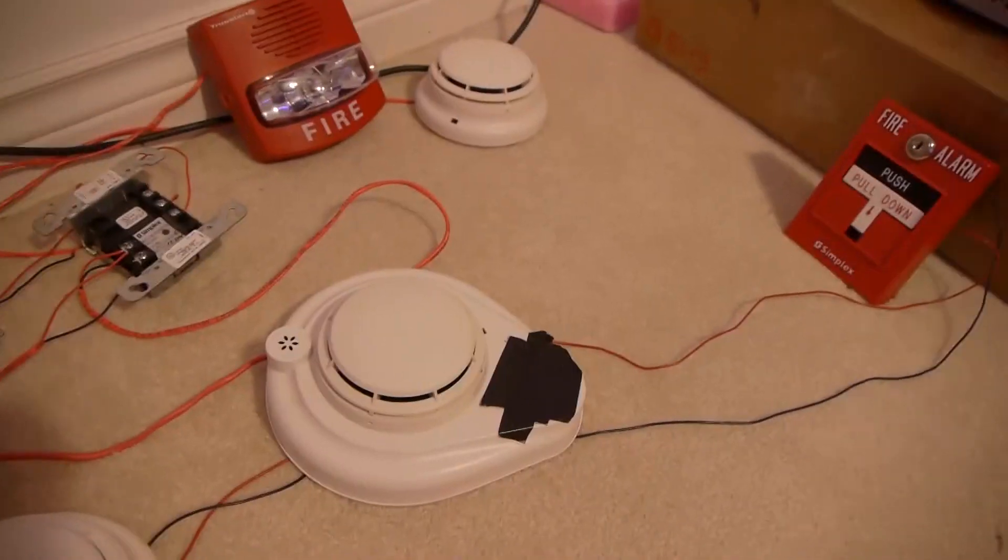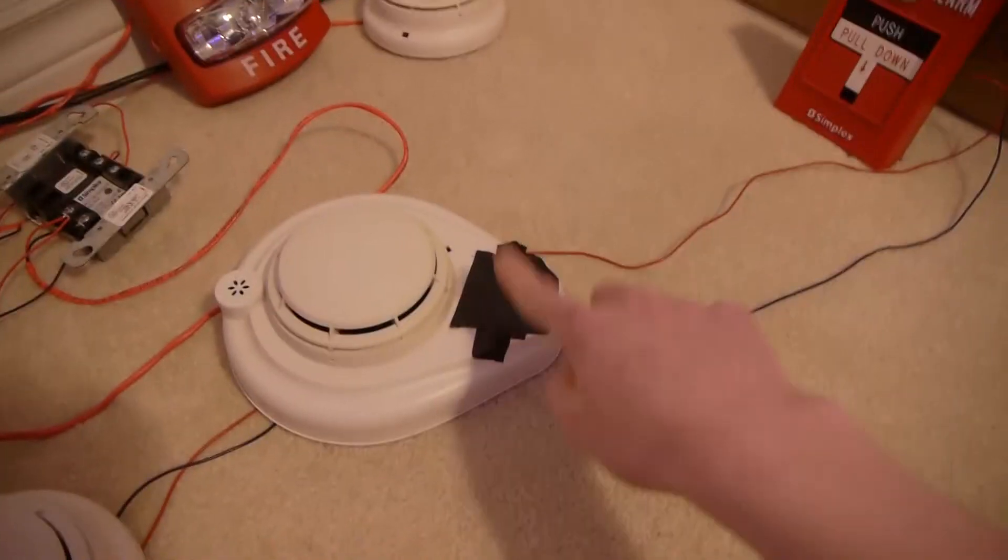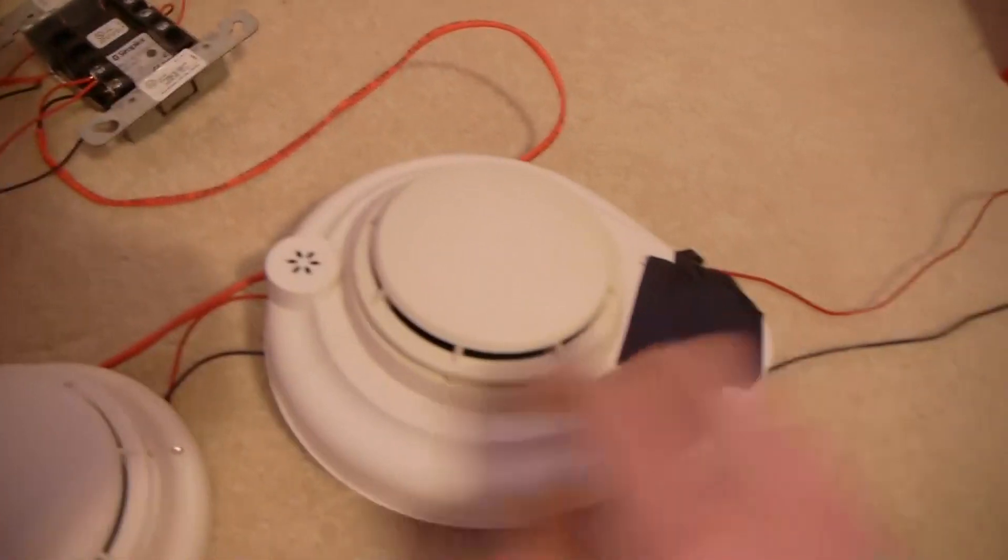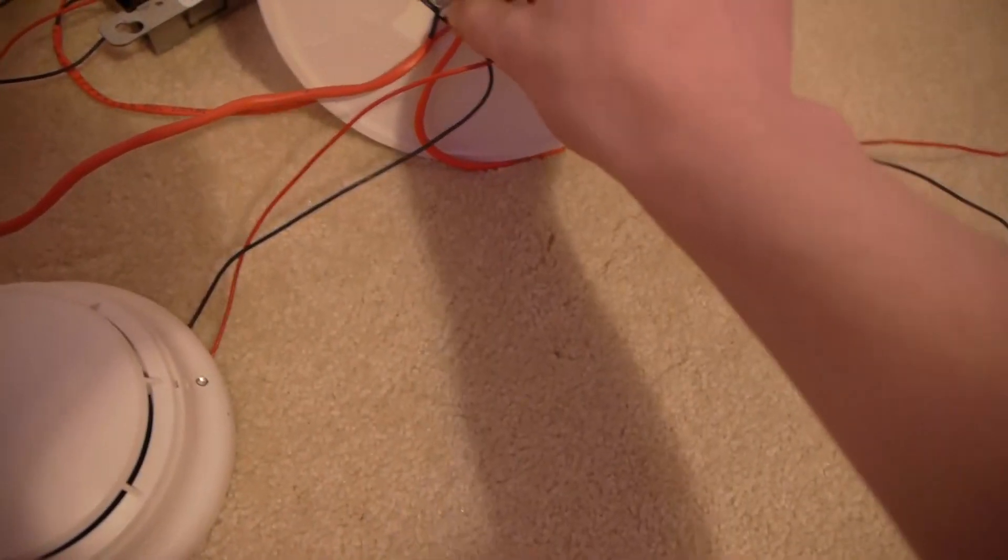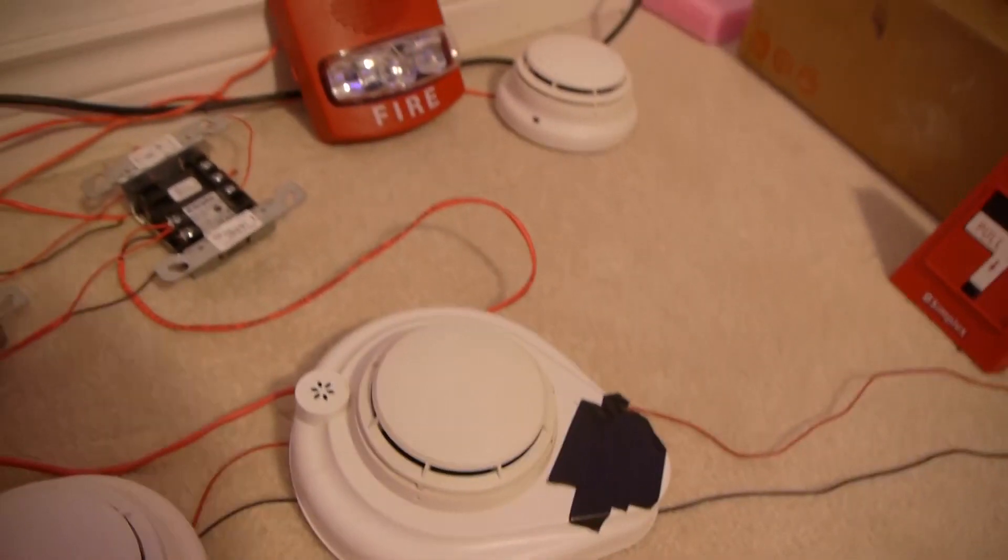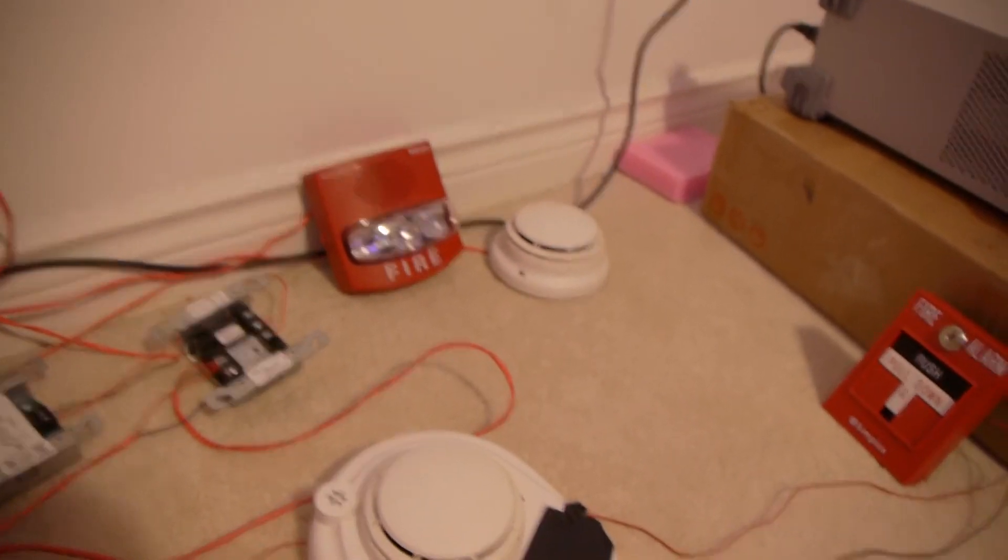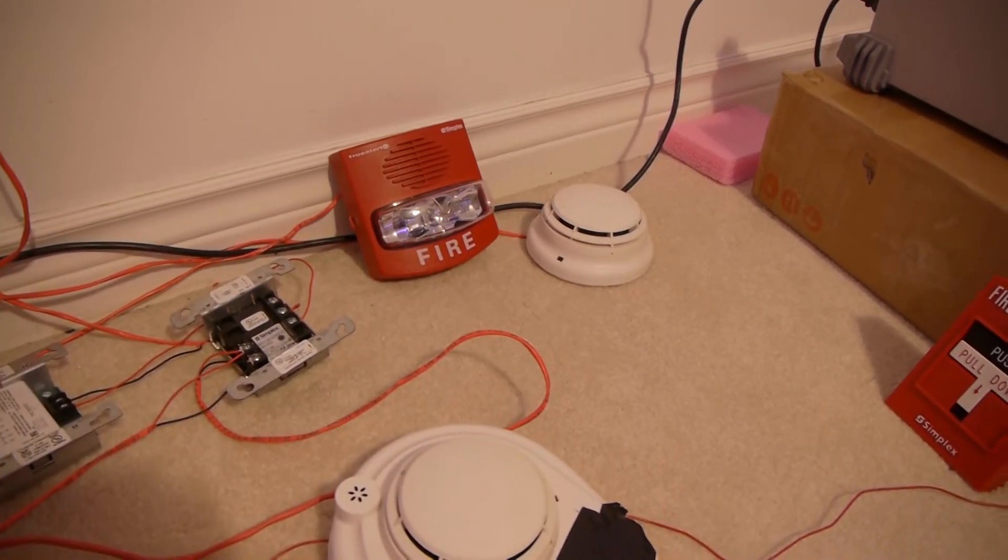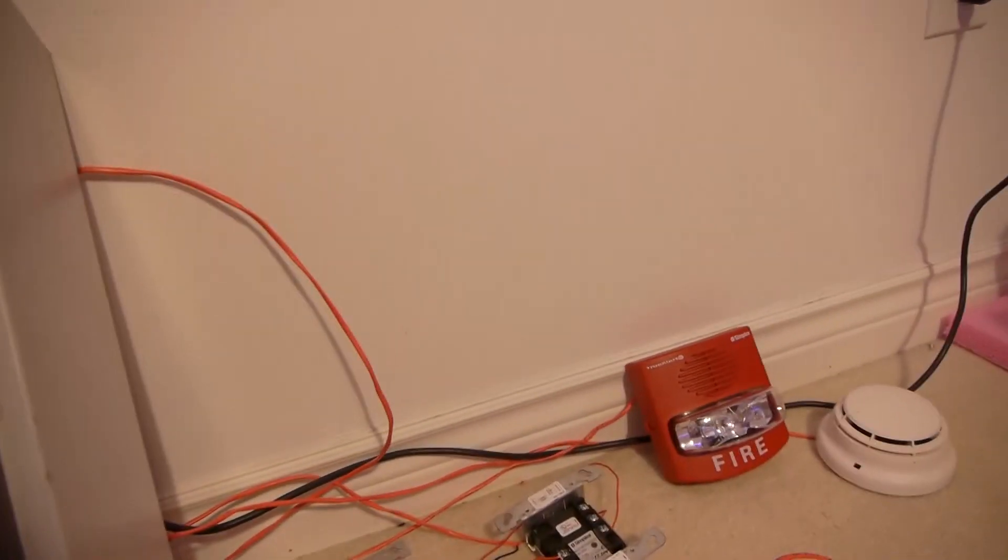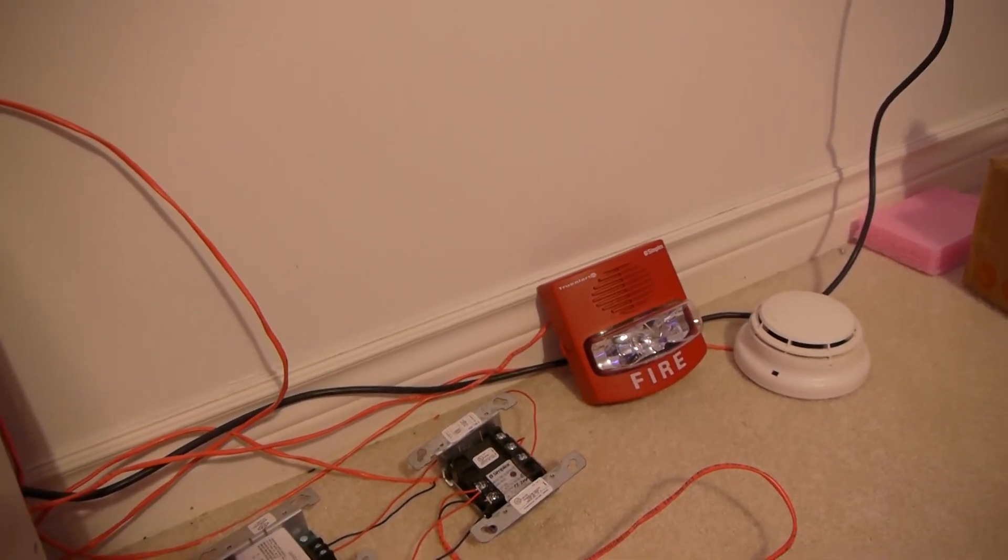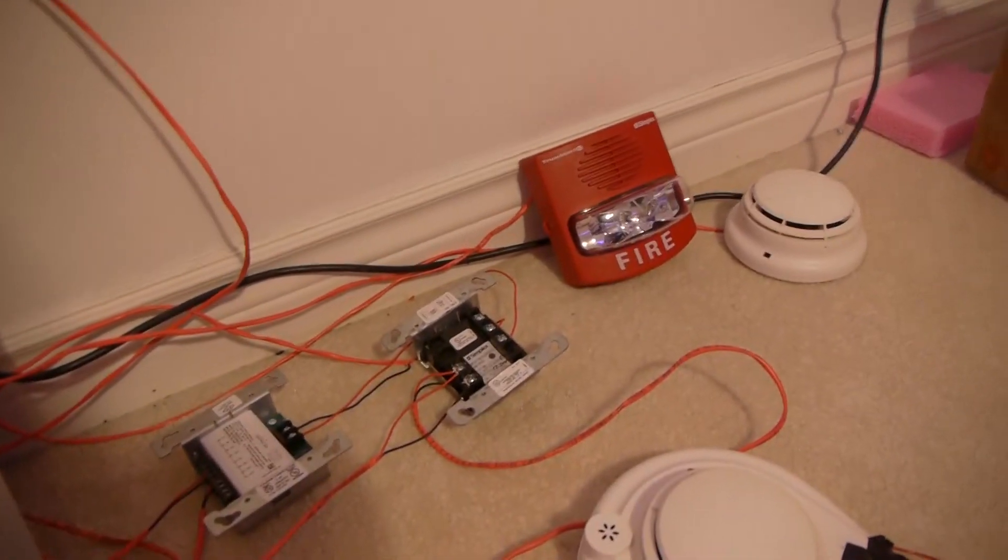Now for carbon monoxide, the standard coding is code 4. Now the sounder base, basically the sounder base is wired up just like a horn. So basically there's two terminals on the back for IDnet, for the carbon monoxide sensor and the smoke detector, and there's two terminals for the horn just like any other horn on the fire alarm system. They're just two wires, and it just gets powered up at 24 volts. Now it is continuous. It doesn't have any coding built into it. So what you need is, normally the coding is done by the panel. Now this panel doesn't have any NAC circuits, so I'm using the panel's built-in relay.